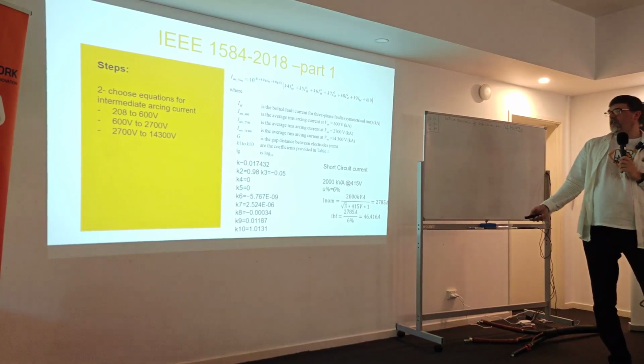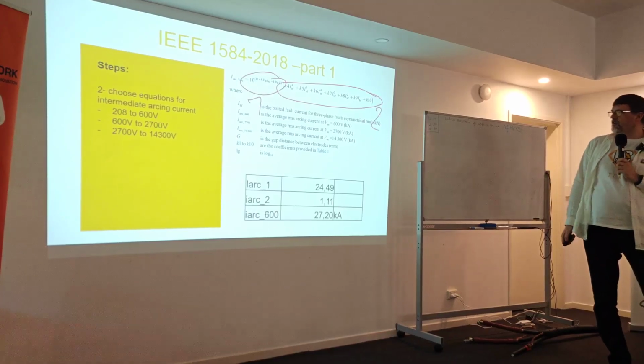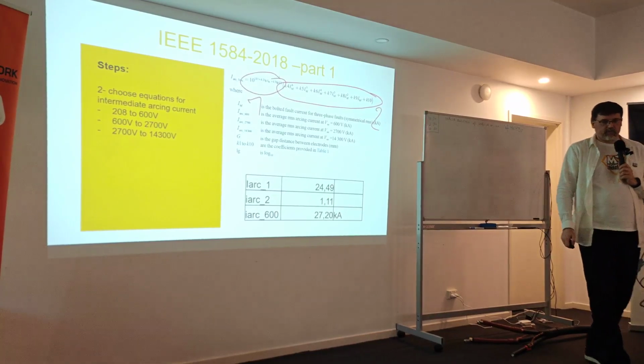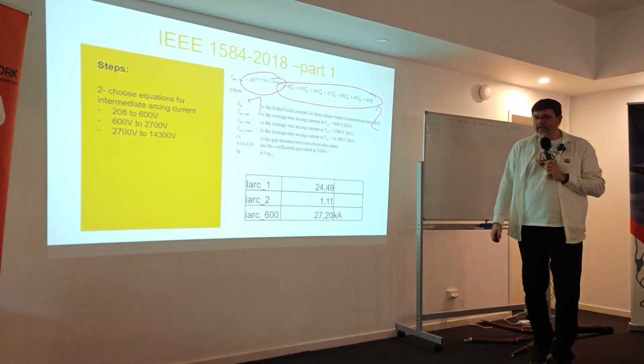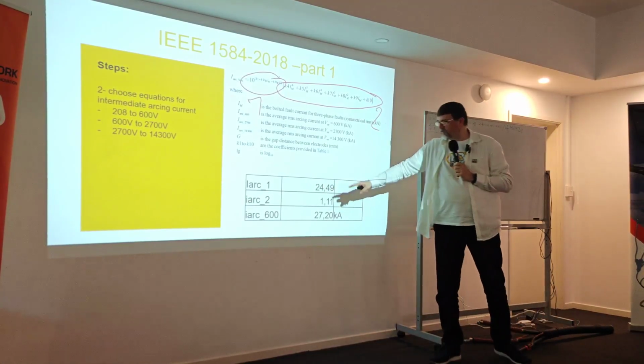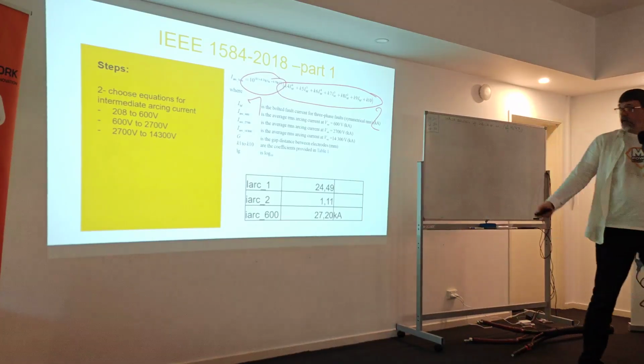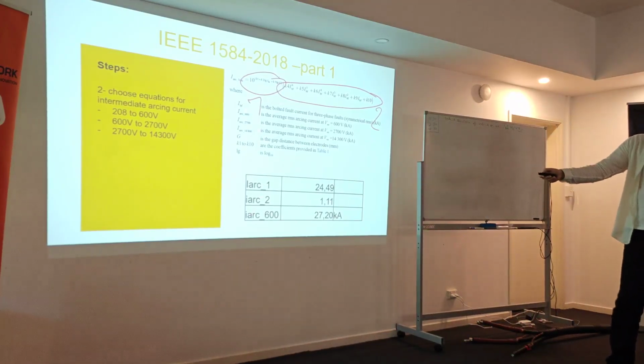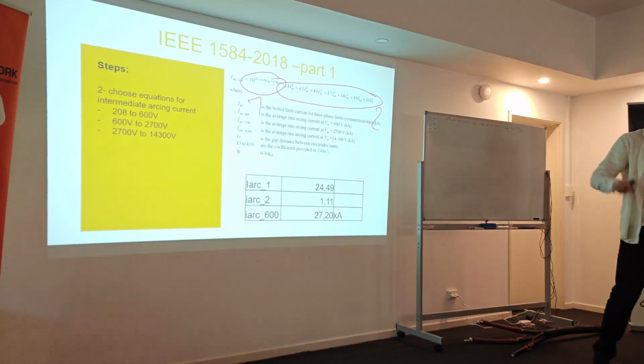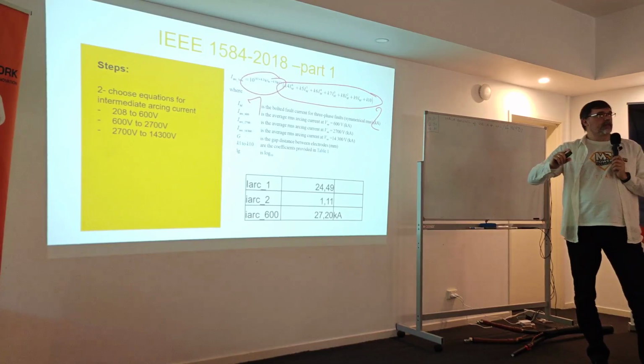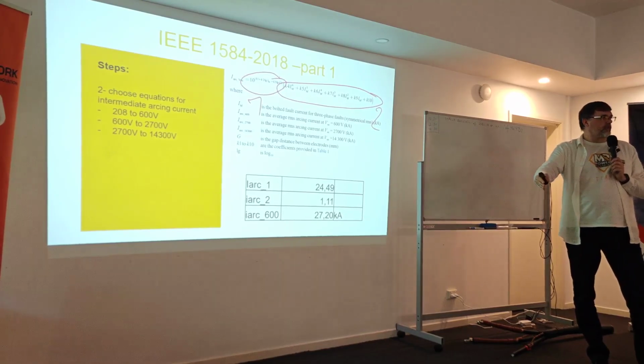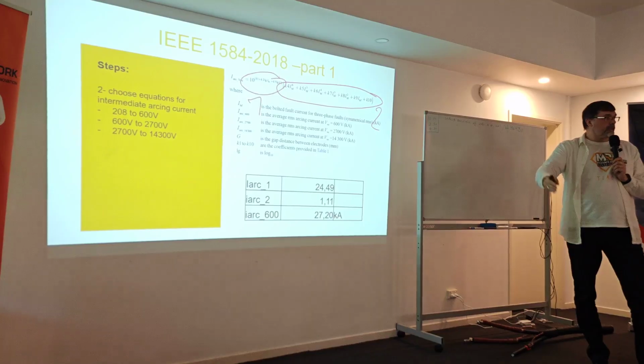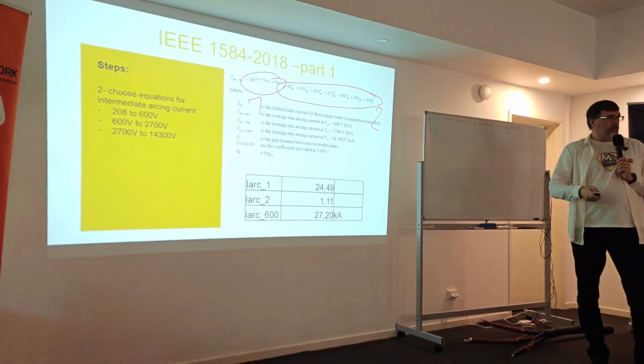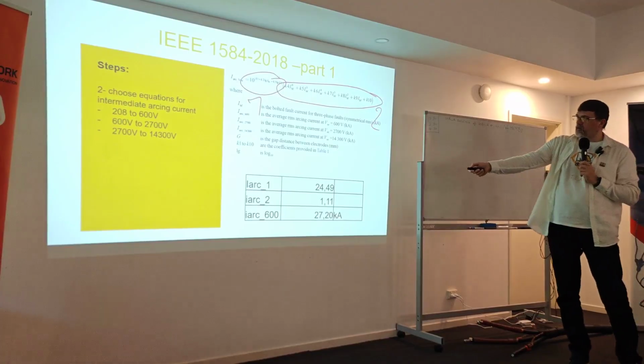I have a bunch of the coefficients, and we go next. So I made some Excel, because I couldn't download in the plane. I have an Excel, 24 was the first step, and I divided the equations in two parts just to make it easier, yeah? So the first part of the equation was 24, the second was 1.1. I end up having 27.2 kiloamp arc current. So you can see that the arc current is not exactly, but it's something like 60% of the bolted fault current, or the short circuit current, which is a big difference for the protection. So that's the one thing, because of the impedance and because of the gap.